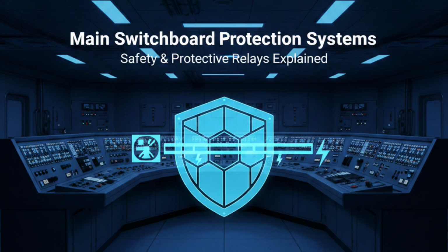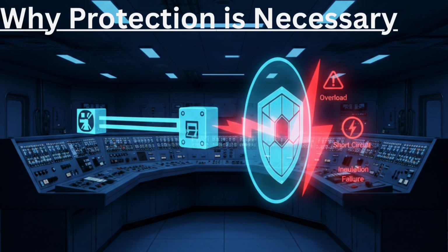Now let's understand why protection systems are necessary. Why protection is necessary. Electrical systems operate under high power and high current. Even a small mistake or insulation failure can create a dangerous condition. For example, if a motor draws more current than its rated value, it may overheat. If two phases accidentally touch each other, it creates a short circuit. If generator fuel supply fails during parallel operation, reverse power can occur. Without protection relays, these faults would continue and cause severe damage.